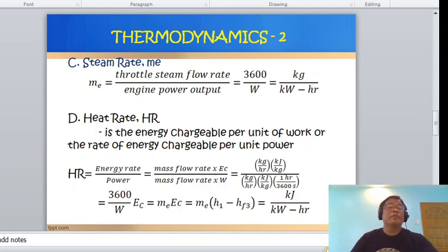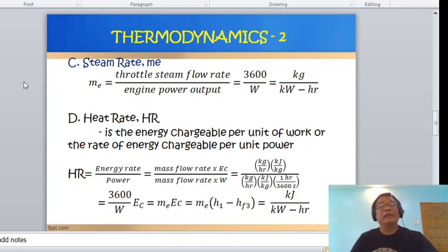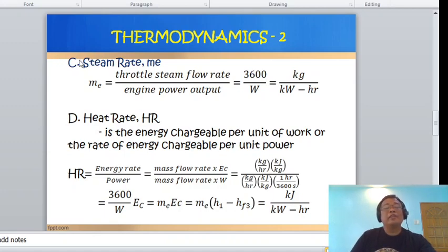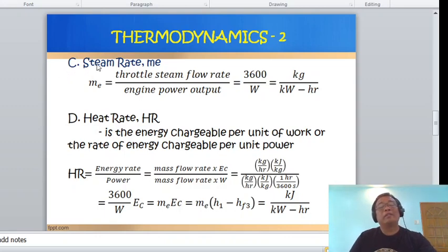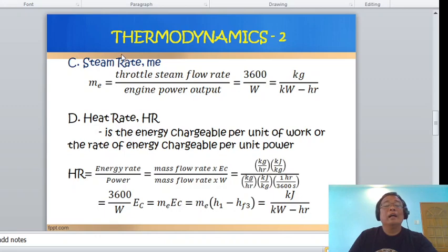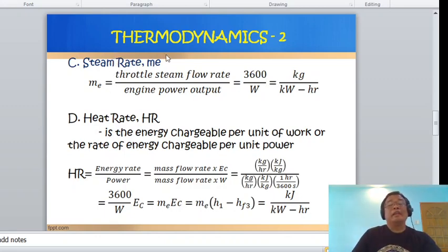Next we have the steam rate, which is equal to the throttle steam flow rate divided by the engine power output. The unit of steam rate is kilogram per kilowatt-hour. The engine power output is mass flow rate multiplied by the change in enthalpy in kilojoules per kilogram. Converting units — multiplying kg/hr by kJ/kg, then changing hours to seconds and canceling mass — the resulting formula for steam rate is 3600 divided by the change in enthalpy at the engine, in kg per kWh.